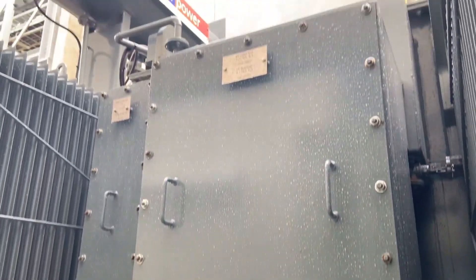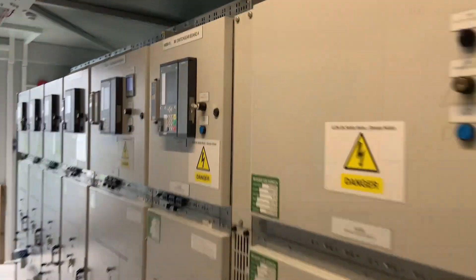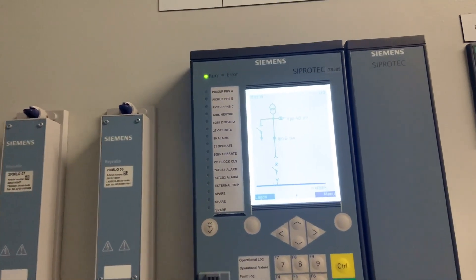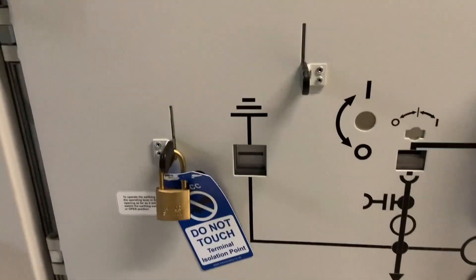You may notice that the old phase colors of yellow and blue are still used for voltages in the high voltage range. The final check was with the 3.3 kV auxiliary switchboard to confirm the incoming switch was in the test position, racked out, and the circuit earth was locked open.